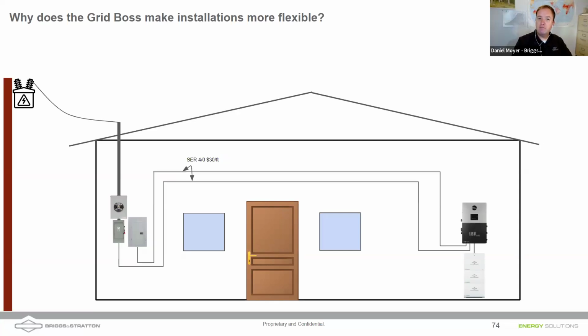I wouldn't recommend that. If I had to, this is probably what I would do: bring 200 amps out of that disconnect, run the entire home's loads all the way across the house, feed it into the 18K PV, come right back out and go all the way back over. We just added hundreds, maybe even $1,000 worth of cable to do this, let alone all the labor as well.